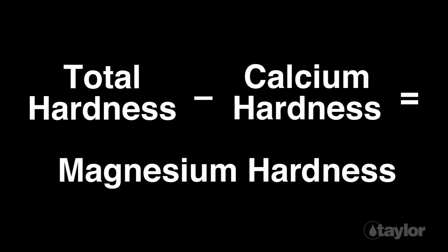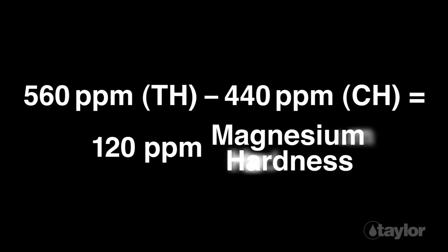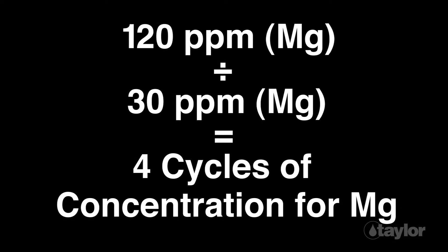With a total hardness level of 140 parts per million and a calcium level of 110 parts per million, the magnesium hardness is 30 parts per million. For discussion purposes, let's assume we tested a cooling water and found a total hardness level of 560 parts per million and a calcium level of 440 parts per million — in this example the magnesium hardness would be 120 parts per million. The magnesium hardness is useful to know, as at neutral pH levels it is more soluble than calcium. For most open cooling water systems, the value found by dividing the cooling water magnesium level by the makeup water magnesium level often approximates the number of cycles of concentration in the system.